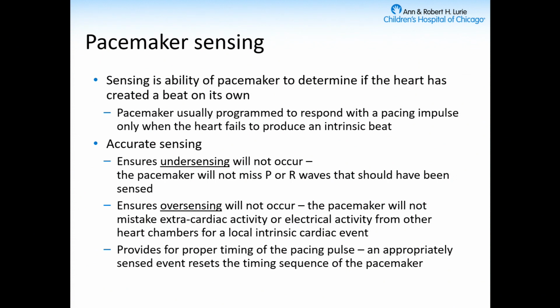So what is sensing? Sensing is the ability of the pacemaker to determine if the heart has made its own beat. And the pacemakers, like I said, are programmed to respond with a pacing impulse only if the heart fails to produce its own beat. Accurate sensing ensures that undersensing won't occur, meaning that the pacemaker will not miss a P or an R wave that should have been sensed. It ensures that oversensing will not occur, meaning the pacemaker doesn't interpret noise or other electrical activity as a local internal cardiac event. And it provides for proper timing of the pacing pulse. An appropriately sensed event resets the timing sequence of the pacemaker and allows all the different intervals that we program in there to work correctly.